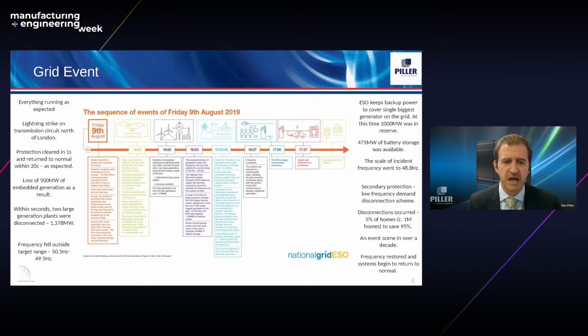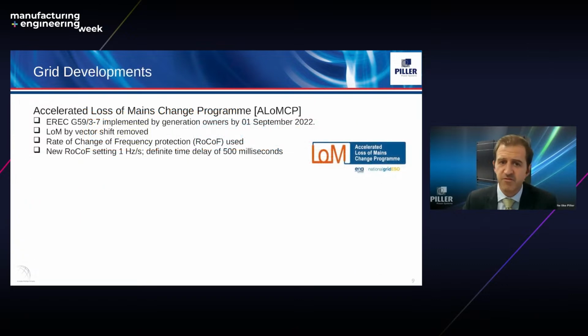We reached 48.8 hertz, and this resulted in secondary protection operating, causing the loss of power to approximately 1 million homes in the country. Now, after this, the frequency began to recover, but we saw critical infrastructure with loss of power, which was a major incident. Following this event, they rapidly rolled out the loss of mains change programme. This was an attempt to avoid similar events in the future.